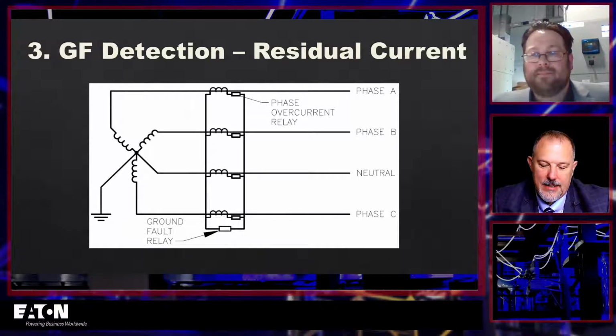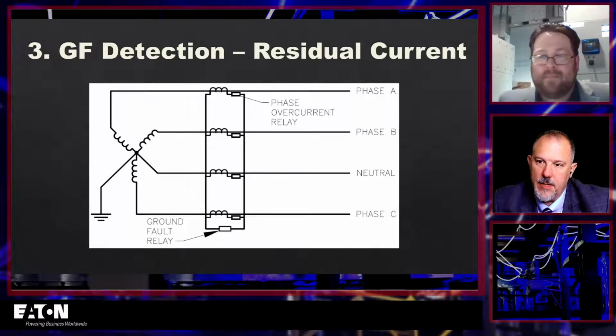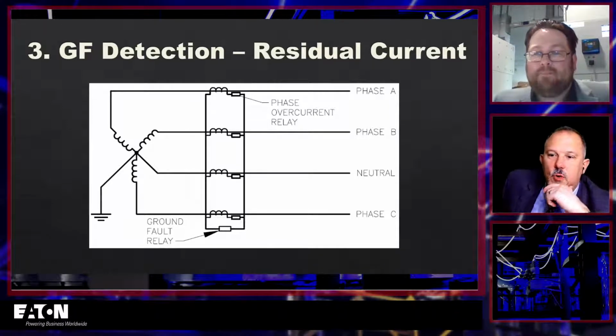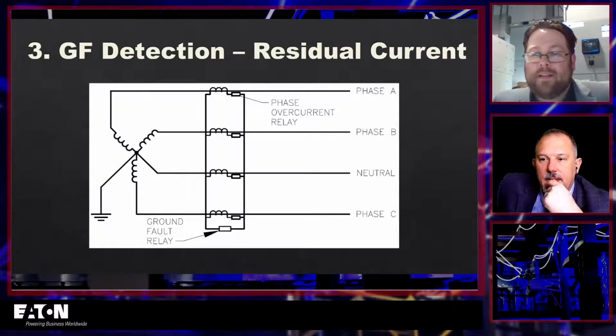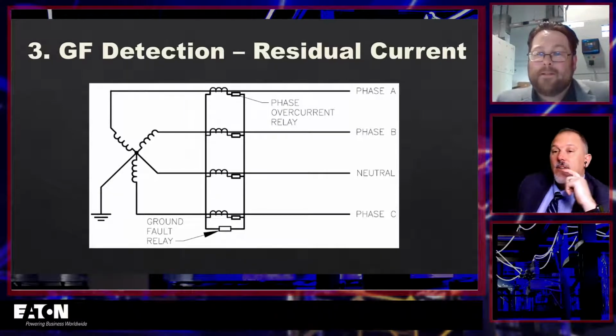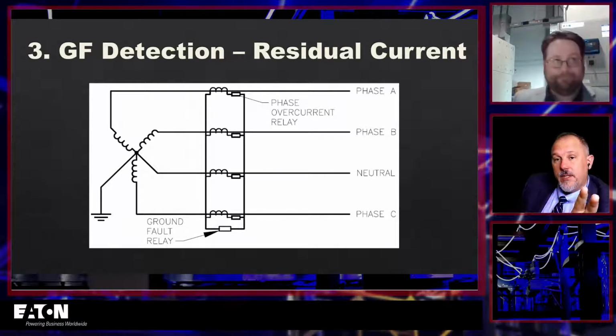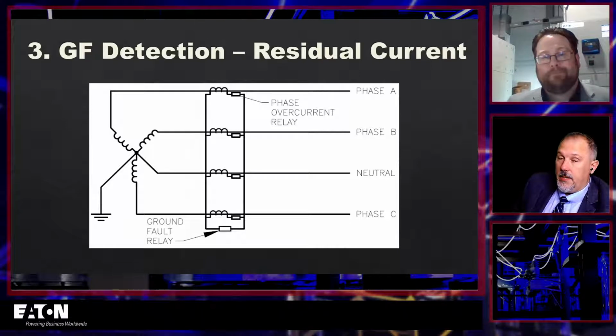Now I see that Bill Neitzel says he ran across a school built in the mid 80s, 480 volt, 1000 amp fused disconnect to an MDP with breakers, no GFP protection. Okay, so my thoughts and fixes. Remember, late 80s, so that would still need to have ground fault protection of equipment. So somebody missed it. If it's fusible equipment at 1000 amps, because it's a fusible switch, it presents some unique challenges.